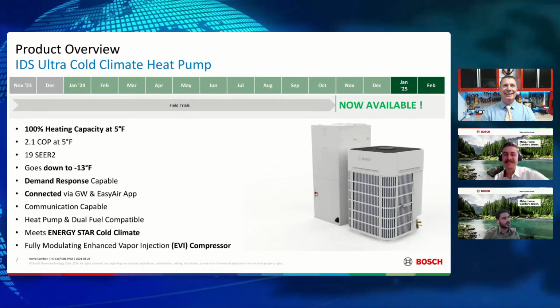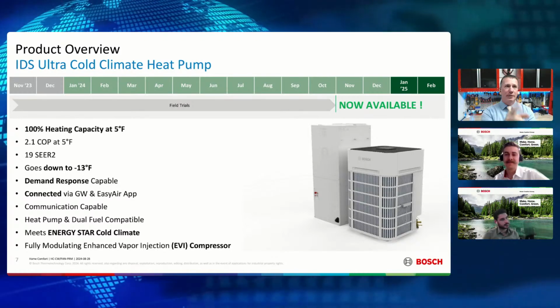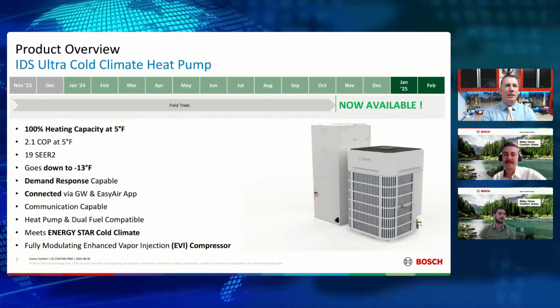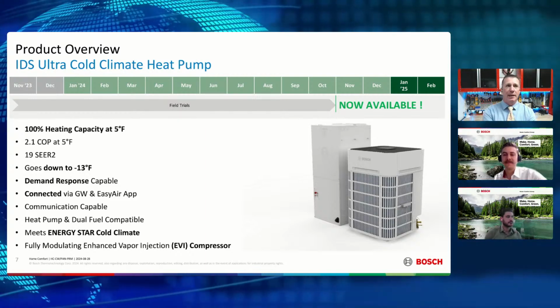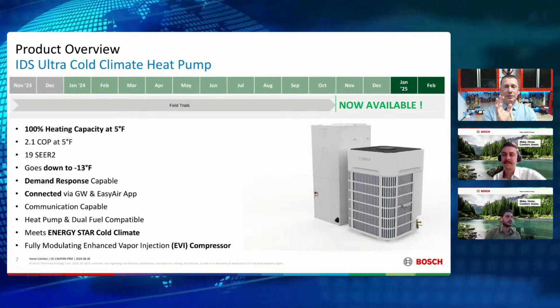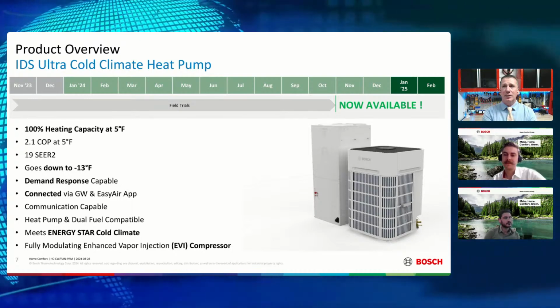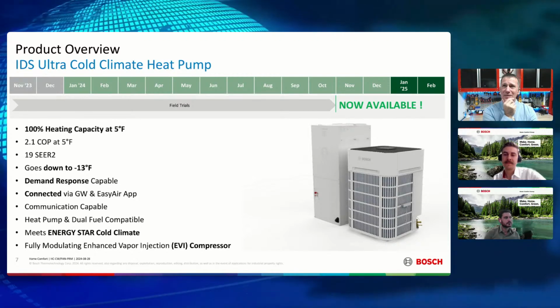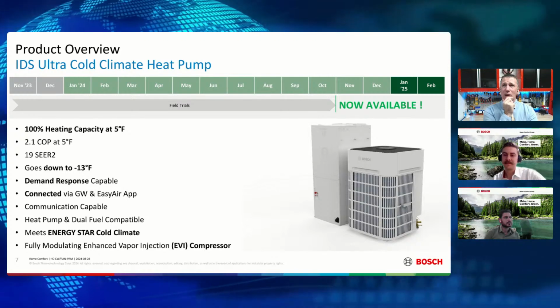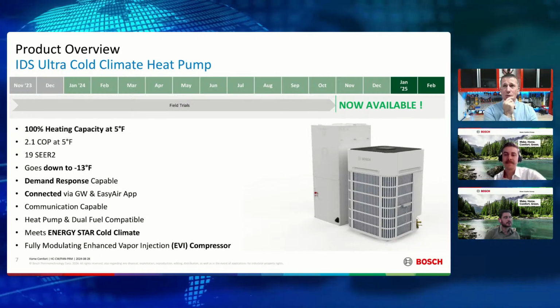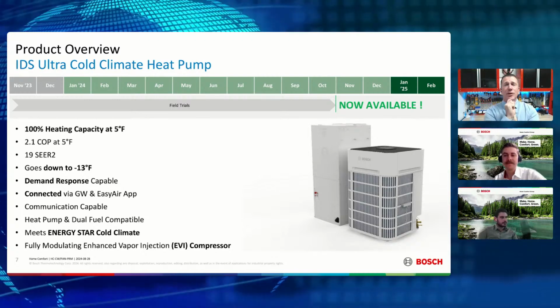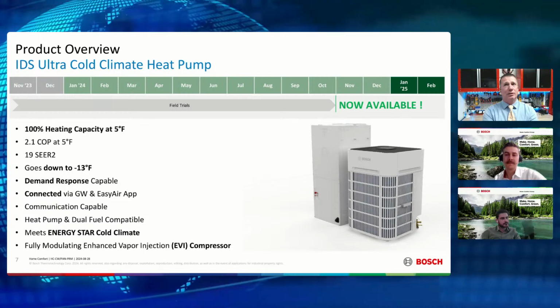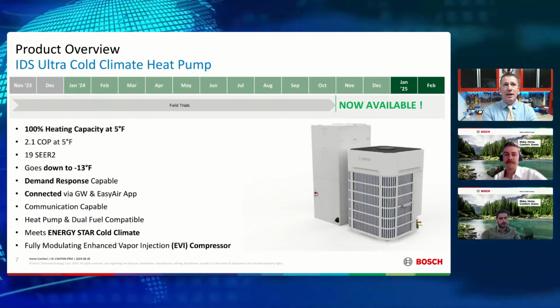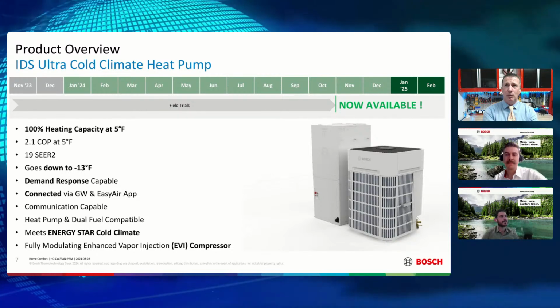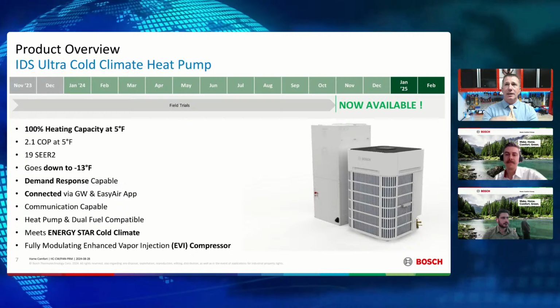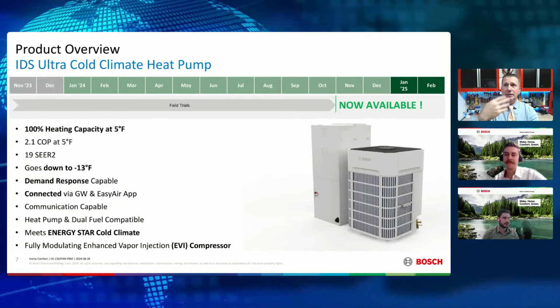Yeah, well, that's really good to know, because I was kind of concerned with that number, because I just did a cold climate heat pump comparison, looking at different pieces of equipment and capabilities at sub-zero temperatures, and there wasn't a whole lot of test data. There was some from AHRI, and I noticed in the extended heating data tables it stopped at minus 13. I'm like, wait a minute. I am pretty positive that they were running that unit down closer to minus 20 when I was at Oak Ridge. And so that makes sense. So if it's already running, so my compressor is already warm, recirculating oil, then I can continue to run down lower than minus 13. So once it gets to its set point and shuts off below minus 13, it's not going to come back on until it reaches minus 13, and then it can reestablish the cycle.